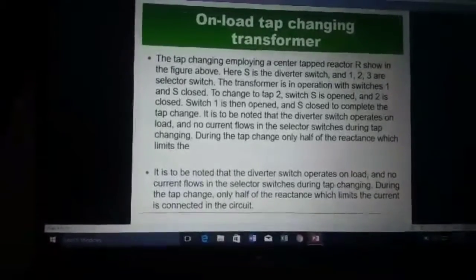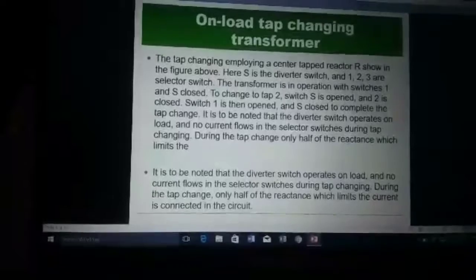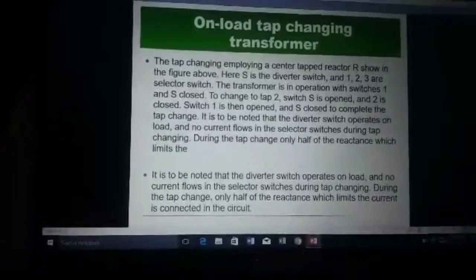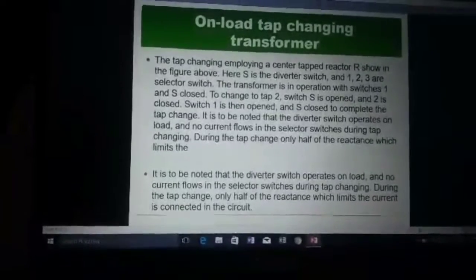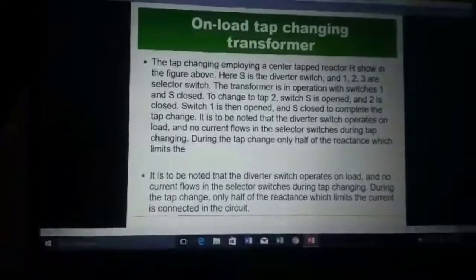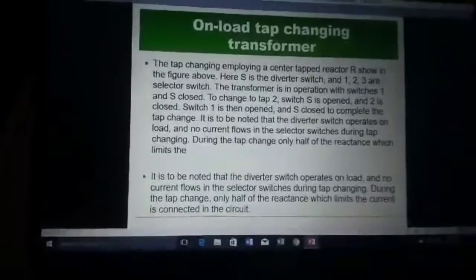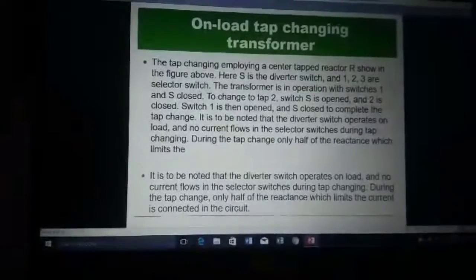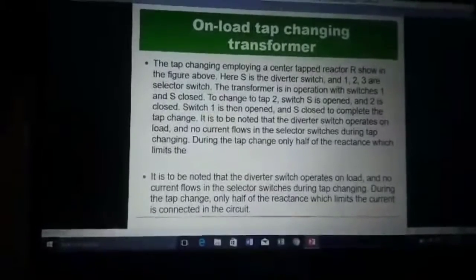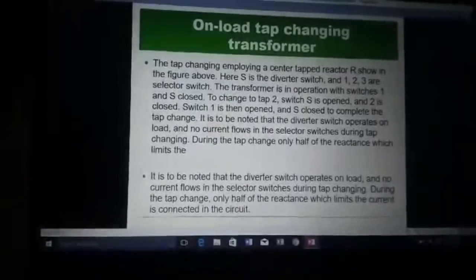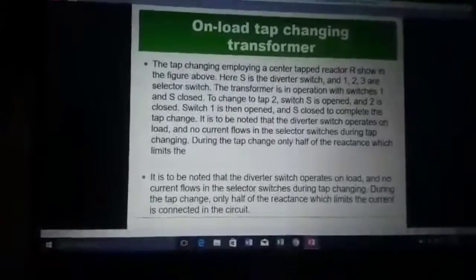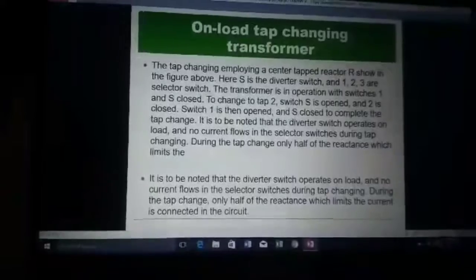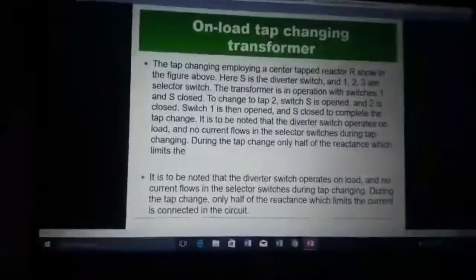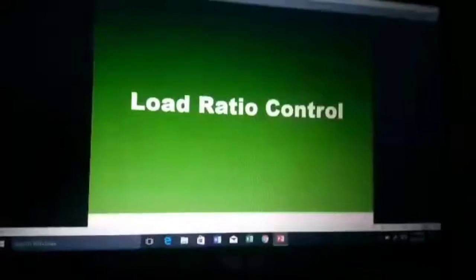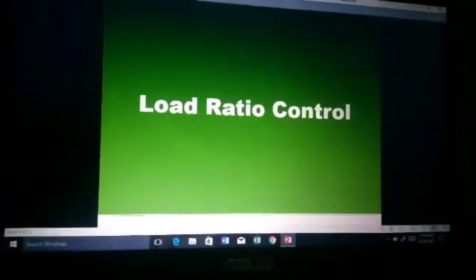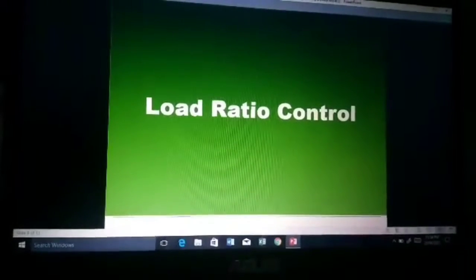It is to be noted that the diverter switch operates on load and no current flows in the selector switches during tap changing. During the tap change, only half of the reactance which limits the current is connected in the circuit. So, lipat naman po tayo sa another topic, load ratio control.